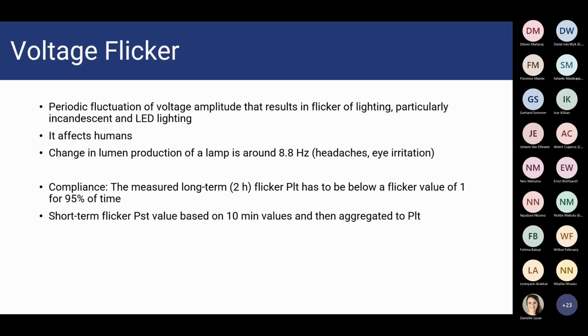Thank you. Yeah, no, thank you, Donnie, for your inputs, and they're all very valid points. It would be interesting to hear from anyone else that's also in the call if you've experienced these and how you've experienced specific loads. But yeah, Donnie, just like you mentioned, on a low fault level, where there's a high impedance, that fast, rapid change in the current will definitely lead to a larger change in the voltage magnitude because of the larger impedance. So you would expect more voltage flicker issues than on other systems.